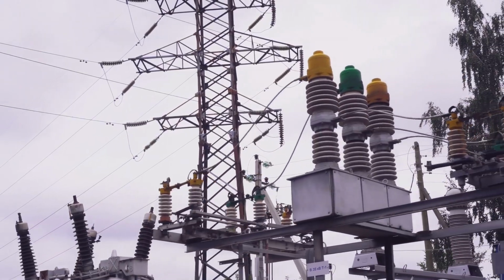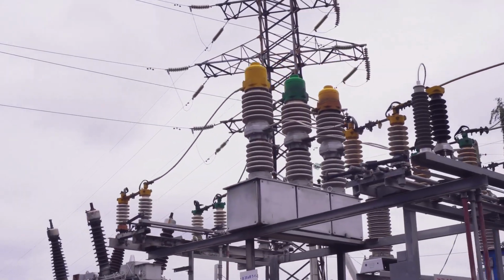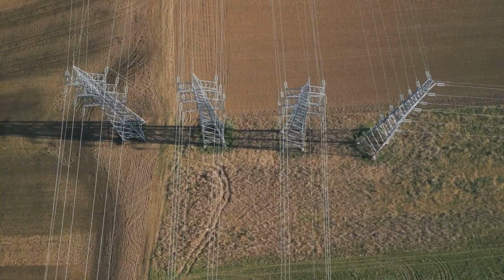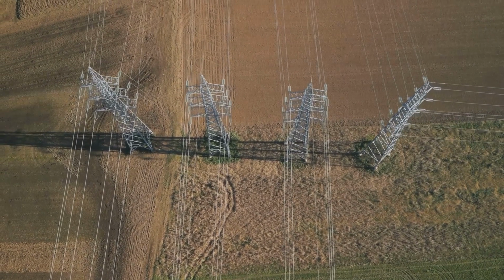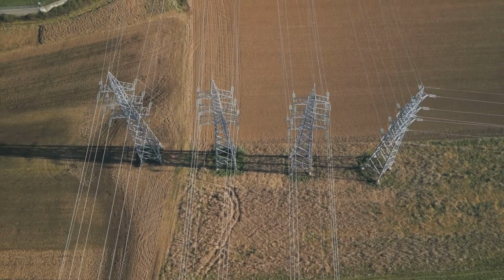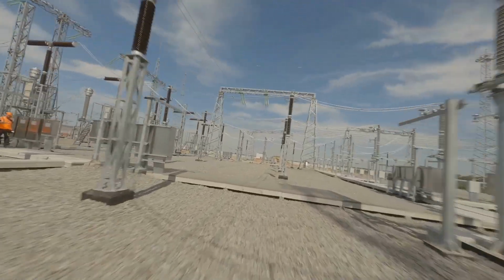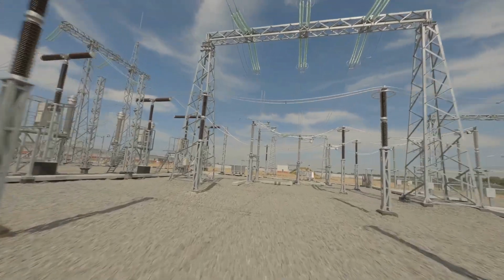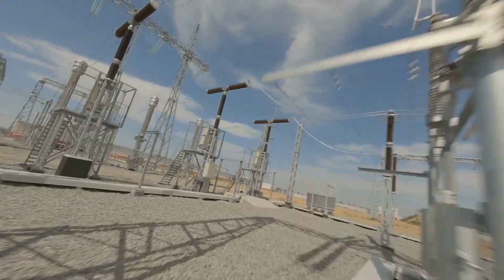Voltage and frequency protection thresholds override curtailment. Communication-based requests are superseded by autonomous response when communication fails. This prioritization ensures that during FRT conditions, DERs focus first on staying connected and supporting voltage or frequency, even if it means temporarily sacrificing optimization or economic performance.